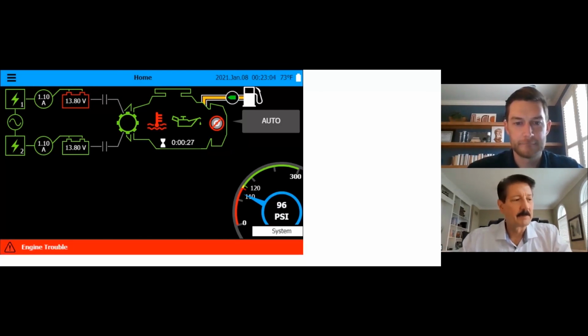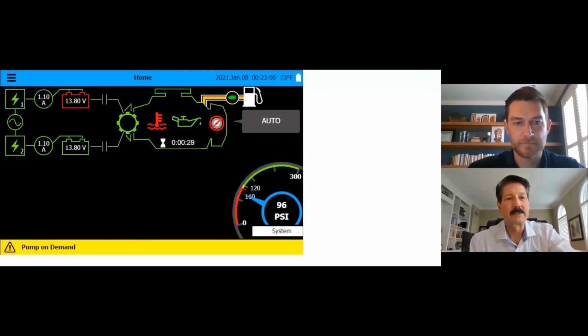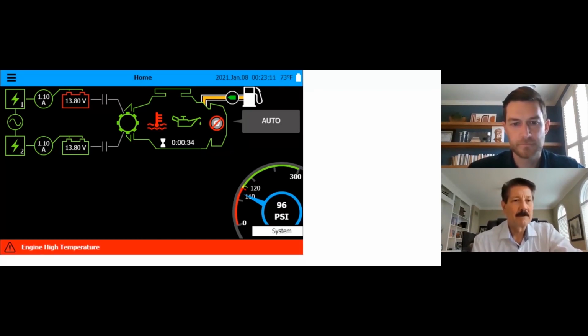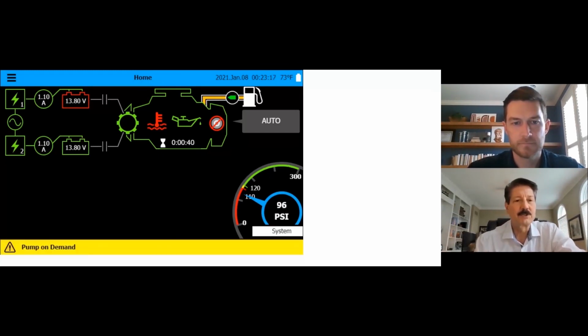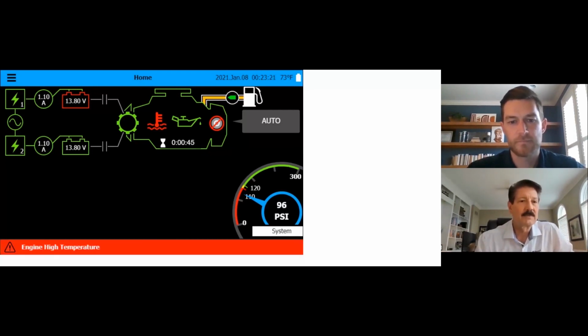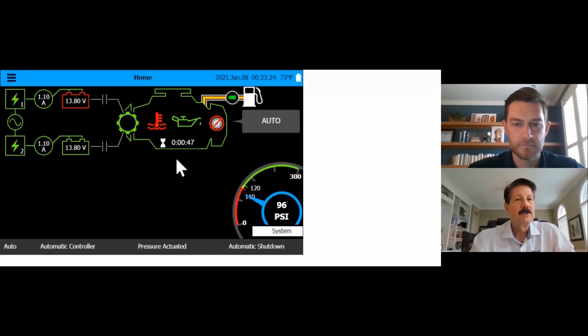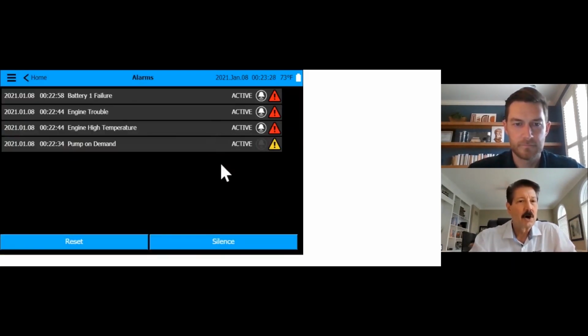So again, for people who want to look at what's going on with the complete system, anything that's highlighted in red is off and non-functioning. And it's really easy. You just look at the screen, and you know there's an issue. Look at the bottom of the screen, and it is giving you all the alarms that it is sensing right now. You don't even have to hit the main menu to the bell and look at all the active alarms you have. Pump on demand, high engine temp, engine trouble, and battery failure, all active right now.